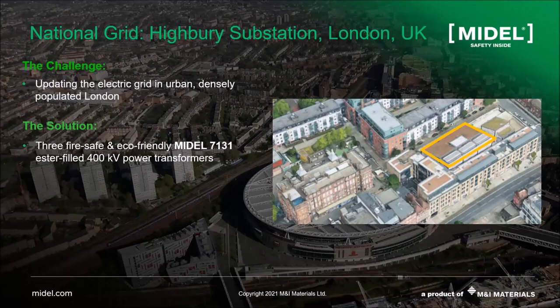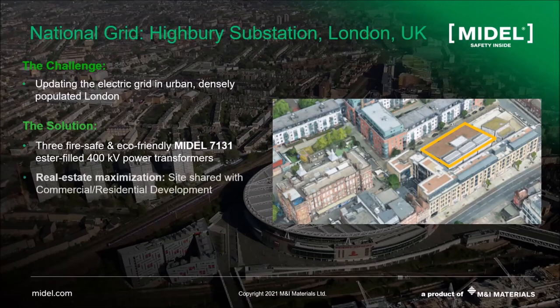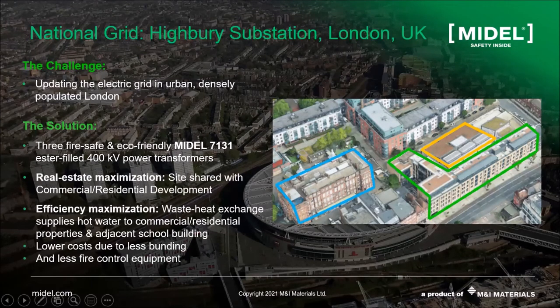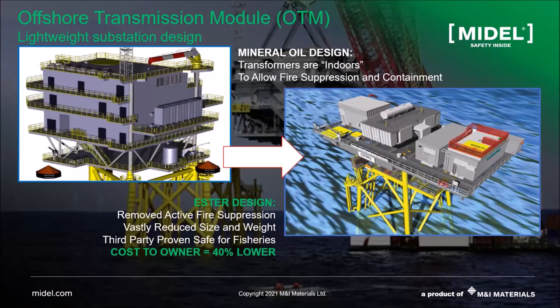And therefore, you were able to build mixed use and residential apartment complexes and buildings all around that new substation, in what used to be the footprint of an entire city block substation. So a lot of innovation used here, and this has been up and running. We've toured it. It's a fantastic case study in substation innovation. On the next slide, we're going to look at offshore wind farms and substations offshore, where formerly the substation was large, with mineral oil filled transformers and almost four stories of infrastructure and building cladding for containment, fire suppression, water collection, you name it. And now the new designs are featuring MIDEL transformers that no longer need all of that complex containment. And there's over 40% savings in just the structural materials, time to construct, and time to install, that you'll see in that simplified and innovative approach.